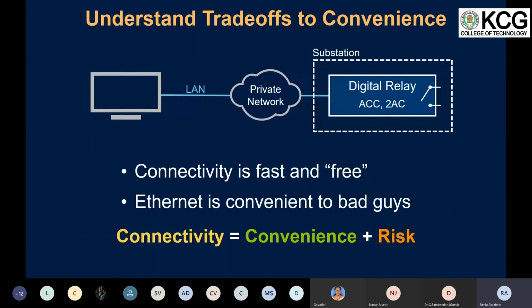For the last few decades, the engineering industry, power industry, and process industry everywhere have seen unparalleled growth in communication links added to digital relays. Many have replaced electromagnetic relays with digital or numerical relays, which are directly connected to the LAN network, to the control room, and then from the control room to the SCADA system for data sharing. Data and other information from relays can easily be obtained at a single location, like the control room, over the LAN network, which is quite convenient. But if this network is unsecure, it can be at higher risk and can be easily compromised.